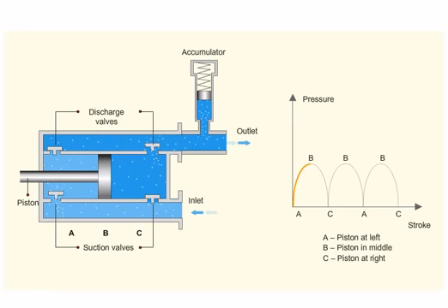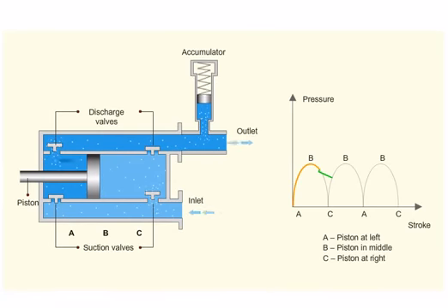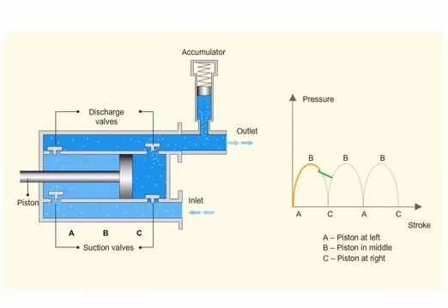As the piston moves to B in its upward stroke, some energy is used to compress the spring. Therefore, the spring has stored energy. At point C, this energy is released when the fluid pressure drops below the compressed spring pressure. The spring now acts like a tiny pump that exerts small additional pressure on the fluid. A sharp drop of pressure is avoided.